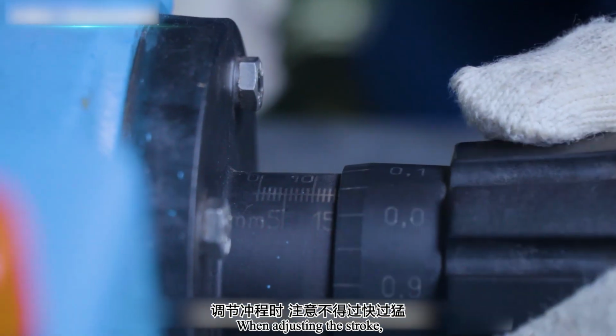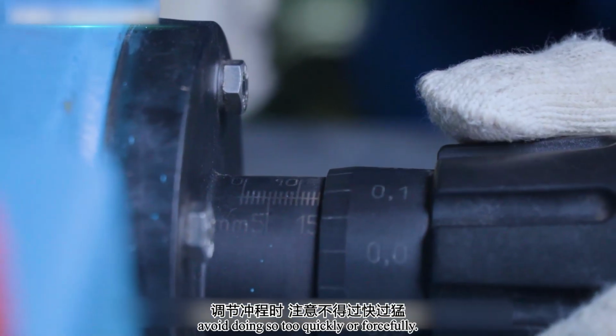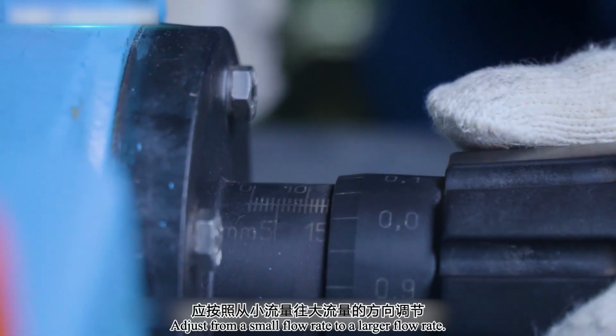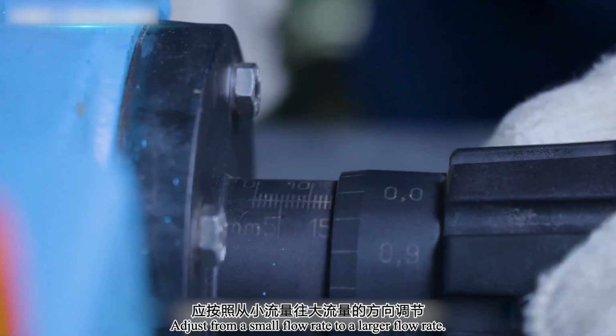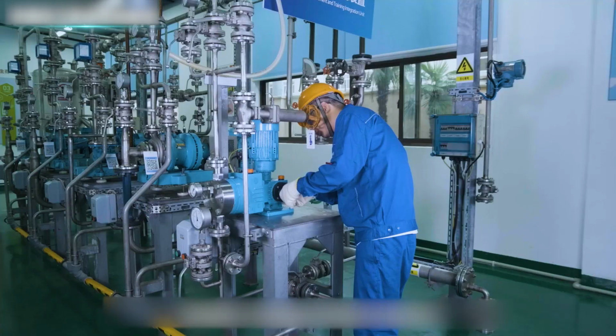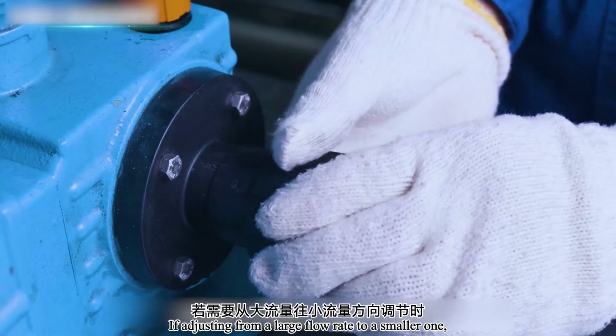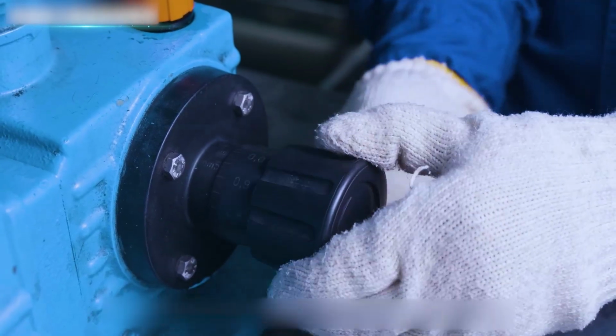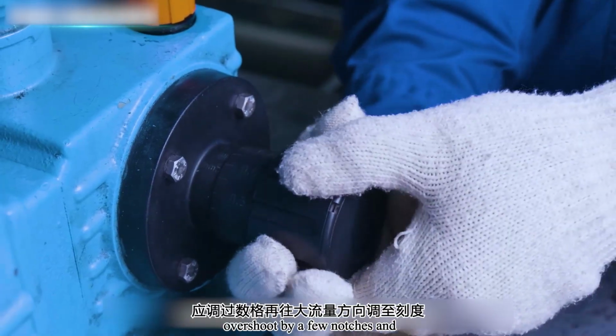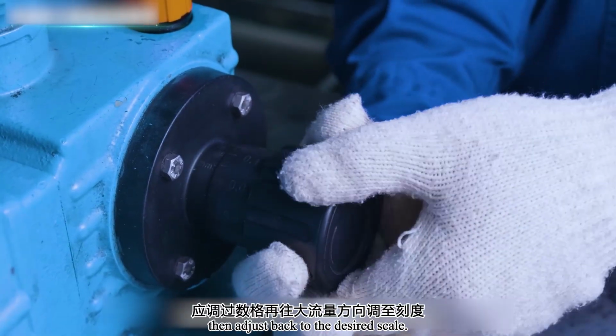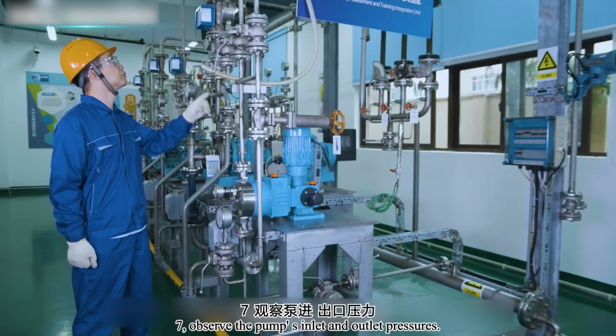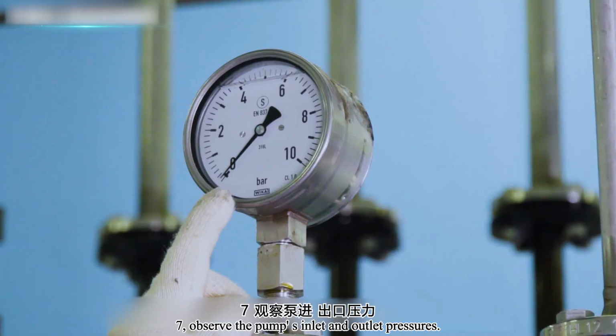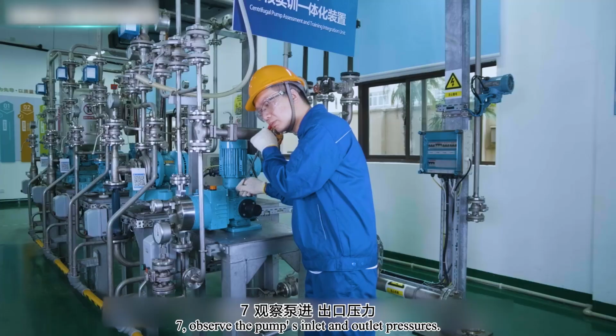Sixth, adjust the stroke to achieve the desired normal flow rate. When adjusting the stroke, avoid doing so too quickly or forcefully. Adjust from a small flow rate to a larger flow rate. If adjusting from a large flow rate to a smaller one, overshoot by a few notches and then adjust back to the desired scale. Seventh, observe the pump's inlet and outlet pressures.